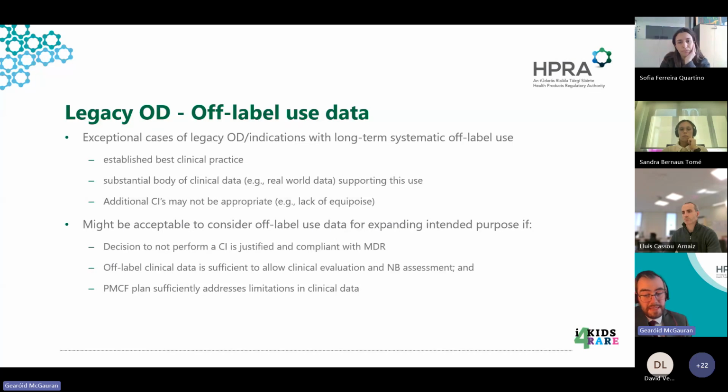With that in mind, it may be acceptable to consider previous off-label use data for expanding intended purposes of legacy orphan devices if the decision to not perform a clinical investigation is justified and compliant with MDR requirements, the off-label use clinical data is of sufficient quality and quantity to allow clinical evaluation and notified body assessment, and the PMCF plan is designed to build on the off-label clinical data to confirm its continued acceptance and acceptable safety and performance for that orphan indication.